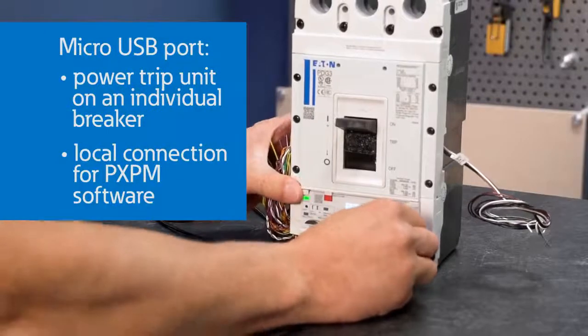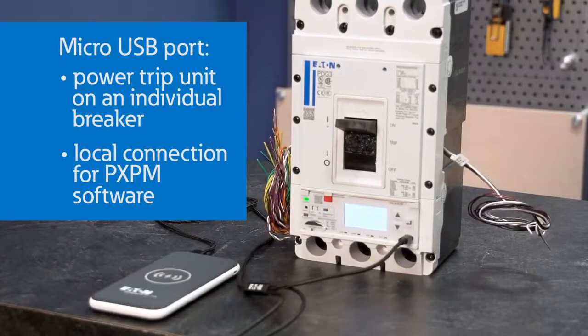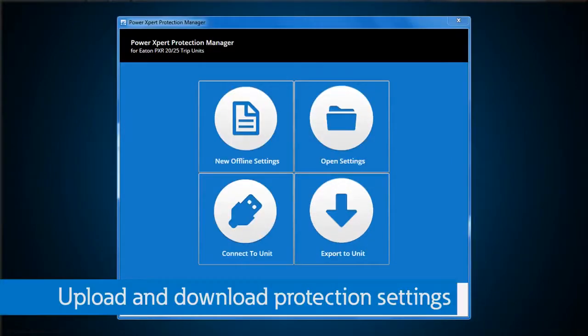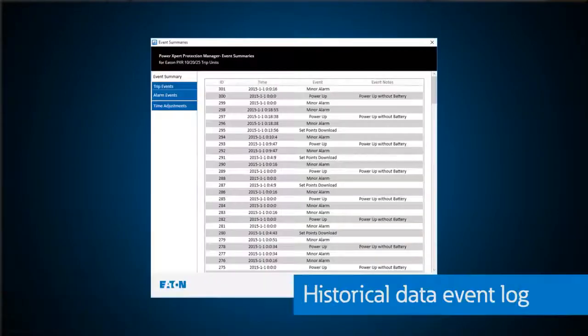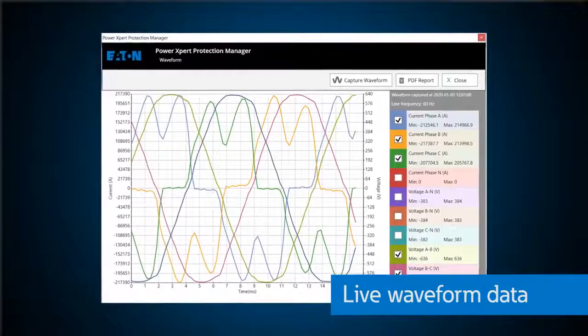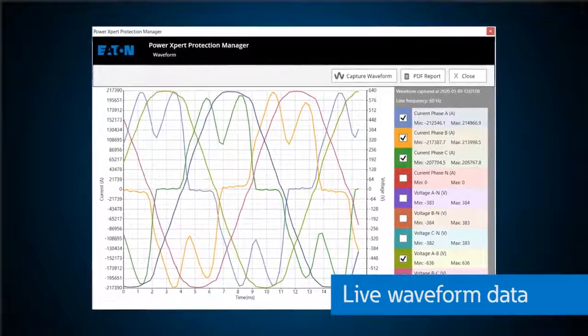All of the PXR trip units have a micro-USB port that can power the trip unit even if the breaker is not installed or powered up. This port is also used to connect to a laptop and our Power Xpert Protection Manager software, or PXPM. PXPM is your one-stop shop to get all kinds of information out of the breaker. You can upload and download protection settings and see the resulting time-current curves. You can access historical data through a comprehensive event log. You can pull live metering data, and you can capture waveform data before and after a fault event.